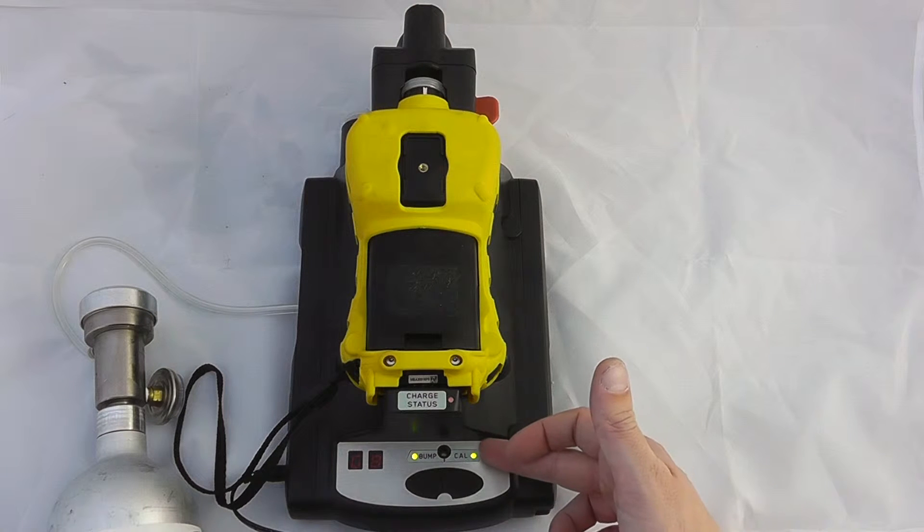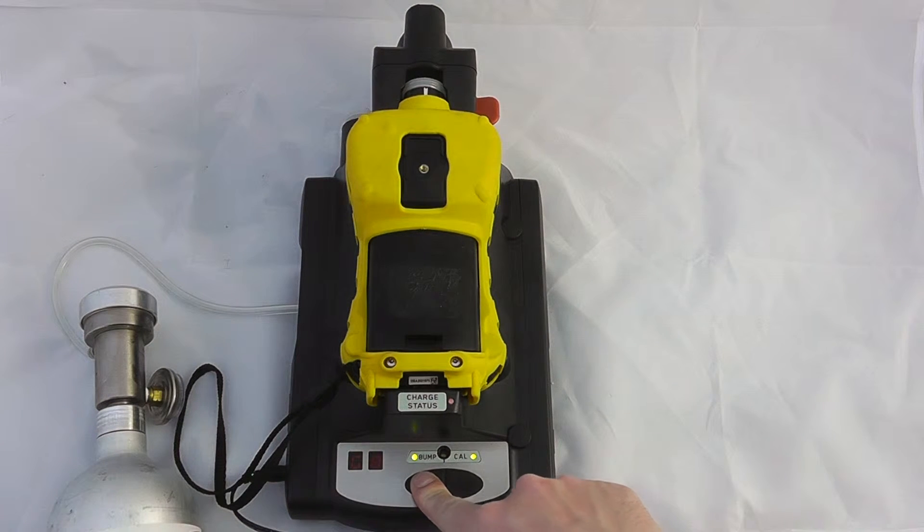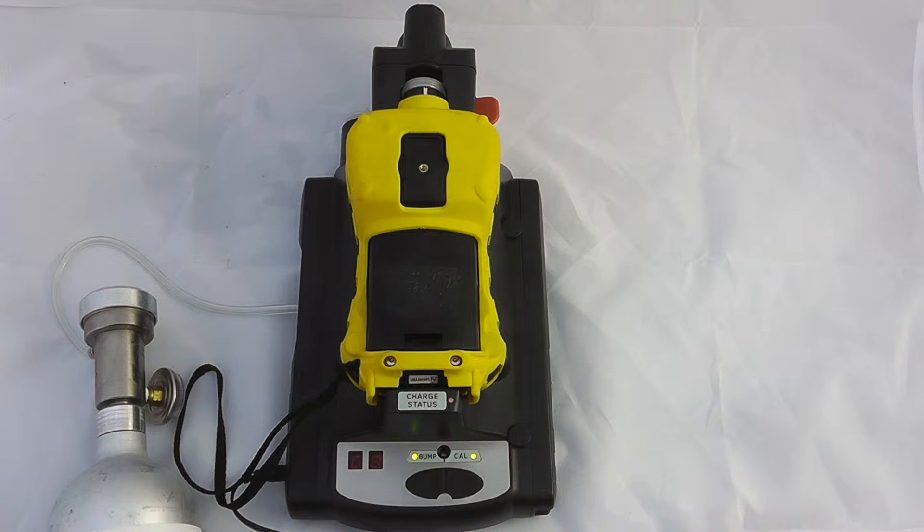Now we have the two green lights on the device so this gives us an opportunity to either bump or calibrate. It is important that there can sometimes be a slight delay on response. It's press and hold for a single bump and then it will go through a bump test.